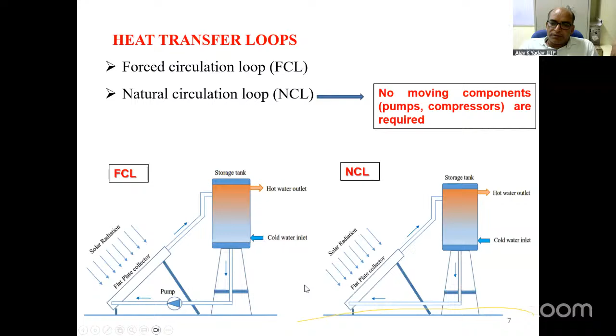There are many places where we use natural circulation. In a power plant, in the boiler part, the furnace and boiler complete part, there is heat generation by burning fuel, and these tubes get heated. Inside that there is water, or CO2 you can say - let's consider water here. So this gets heated and circulates like this, so there is no pump here for recirculation inside the boiler. The furnace is part of the boiler, inside there is a boiler drum and tubes. So there is no pump here. If you put a pump, you would need a huge amount of power to recirculate it, so you cannot use it, because whatever energy you are getting, you may need to supply a good amount of that just to circulate the water. So we use natural circulation only.